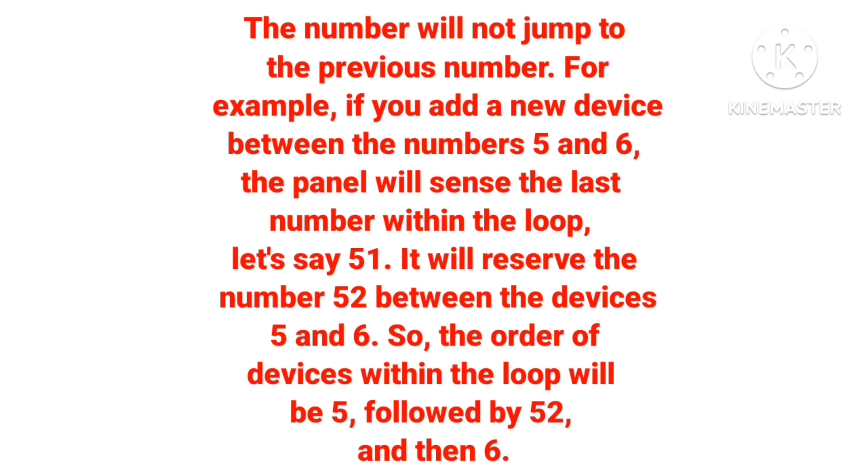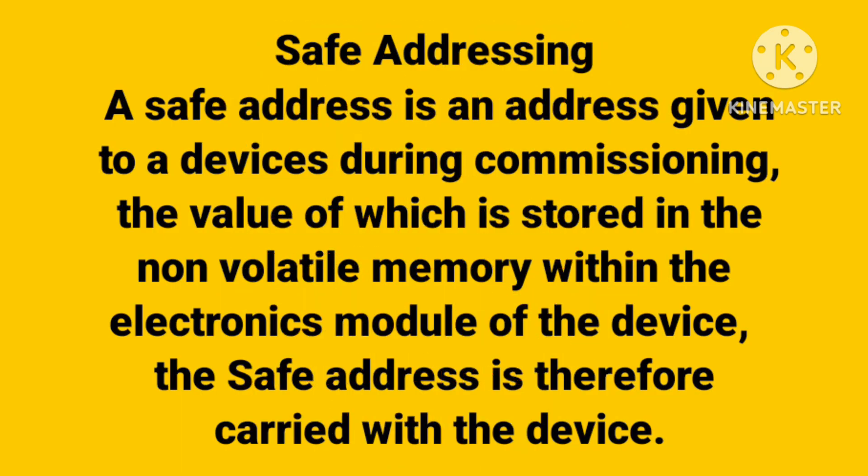Safe addressing is an address given to a device during commissioning, the value of which is stored in the non-volatile memory within the electronics module of the device. The safe address is therefore carried with the device itself — meaning it is stored in the memory of the device, whether that is a module, MCU, or any other device.